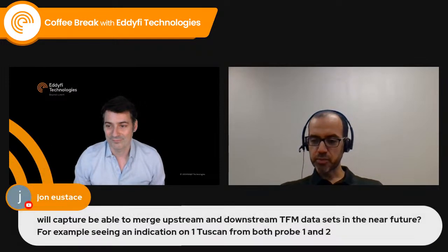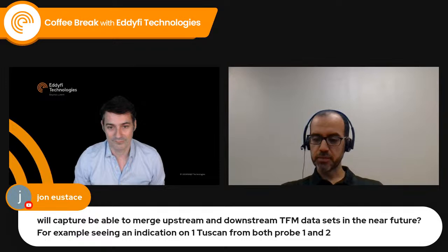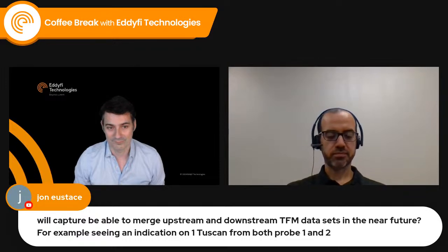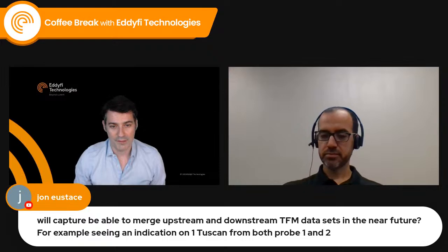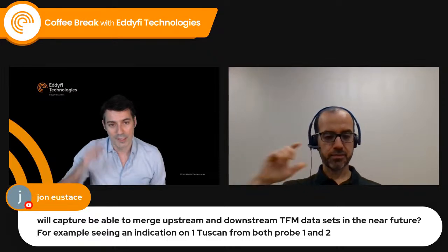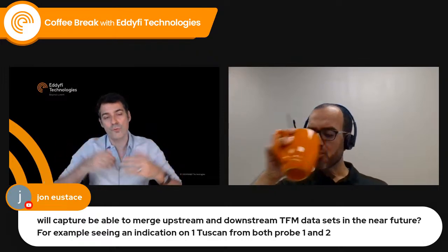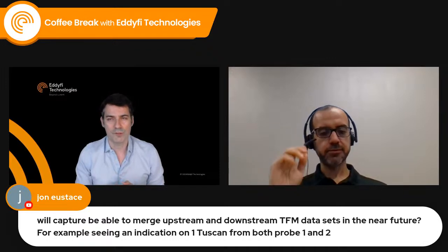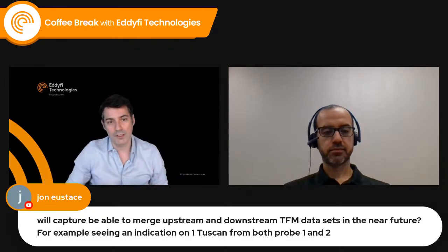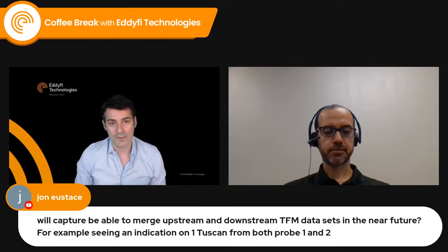We have another question: will Capture be able to merge upstream and downstream TFM data sets in the near future, for example seeing one indication from both probes? Actually already, if you do TFM with 2 probes, since Capture 3.2 which was released back in March, we can do multi-group, multi-mode. We can do TFM from both sides of the weld, which you have to do for weld inspection, and you can merge the data in 3D from the 2 probes.